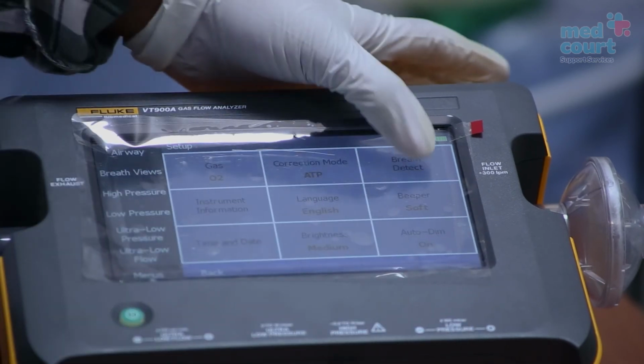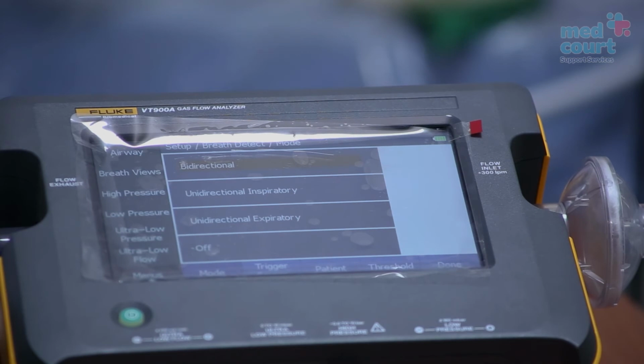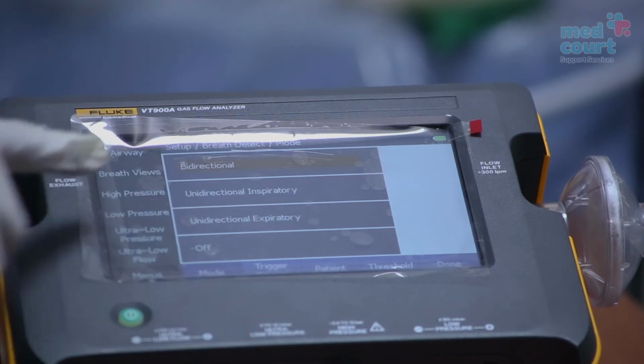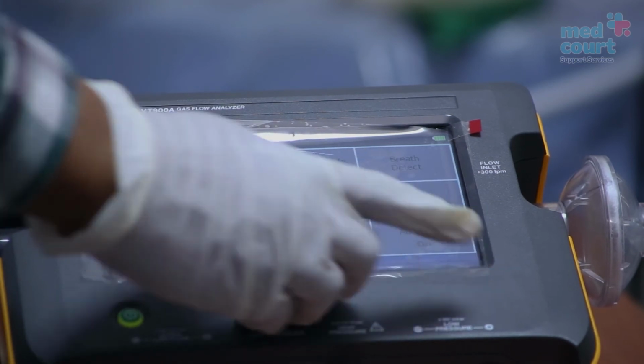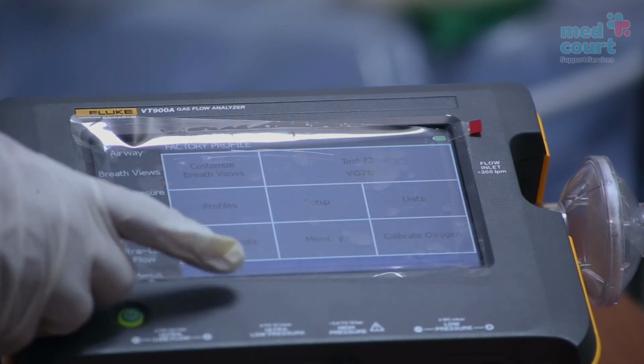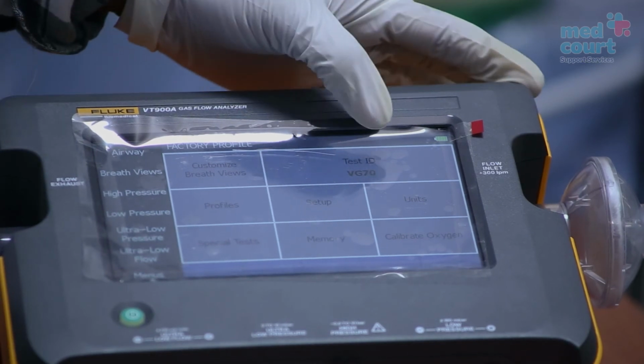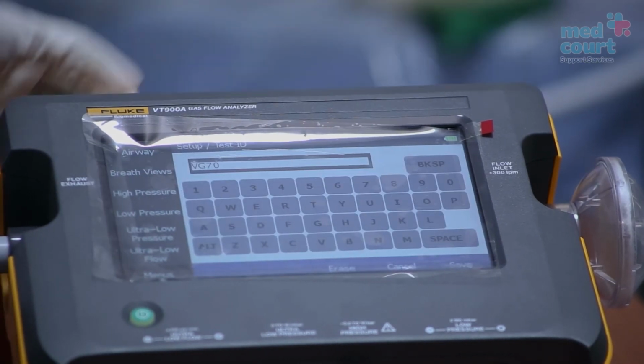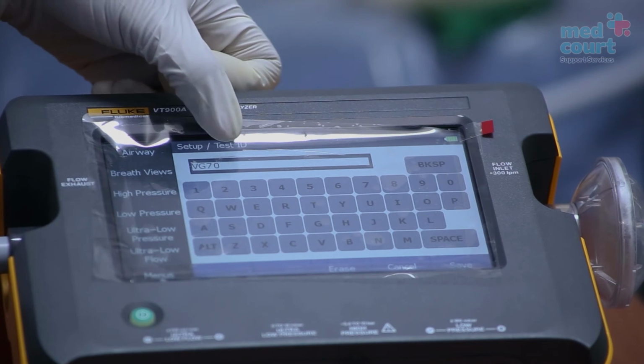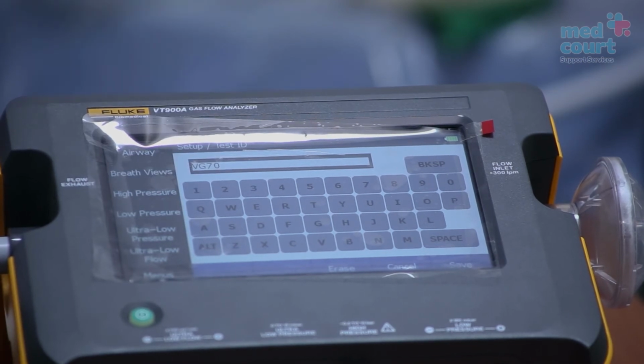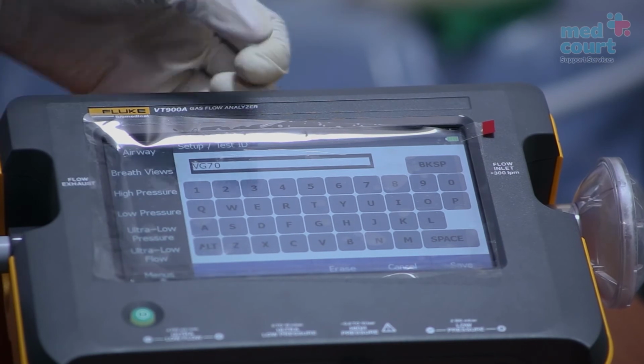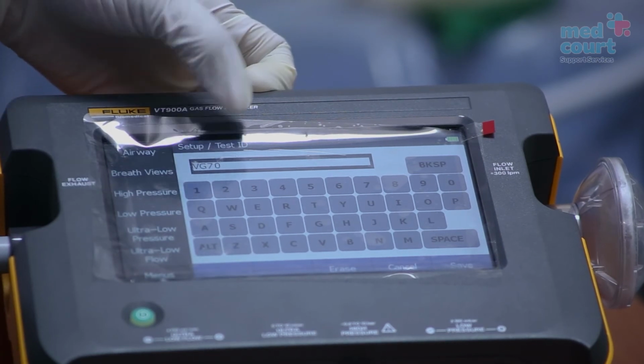For the breath detect mode, it should be set on bidirectional, as the ventilator will be using the inspiratory and expiratory flow. Select bidirectional and click Done. Go back to the main menu. Click Test ID and type whatever information you need to save for this particular gas flow equipment. The model of the equipment has been typed here. Click Save.